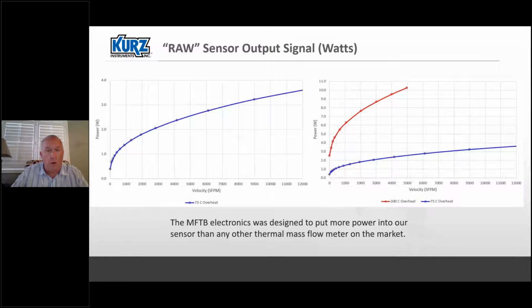So 0 is a data point in the calibration. You'll see 0 watts on all your calibration certificates. You can verify the meter's integrity even with no flow in the line by looking at, say, the 0 flow power and the temperature. You can make some first order assumptions about the health of the device.